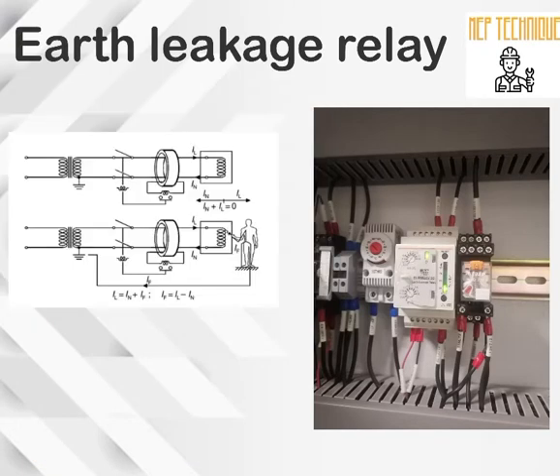We will now understand how it works. The figure illustrates the operation of the core balance leakage device. When the system is under normal conditions, the phase current and neutral current will be equal and in phase, so the CT — that means current transformer — will not detect any current. Under normal circumstances, line current plus neutral current is equal to zero. Just remember Kirchhoff's law: the sum of all currents meeting at a point is equal to zero.